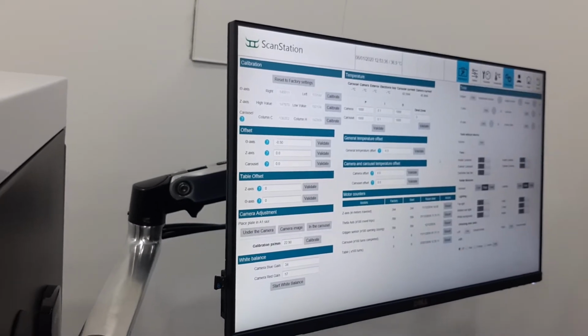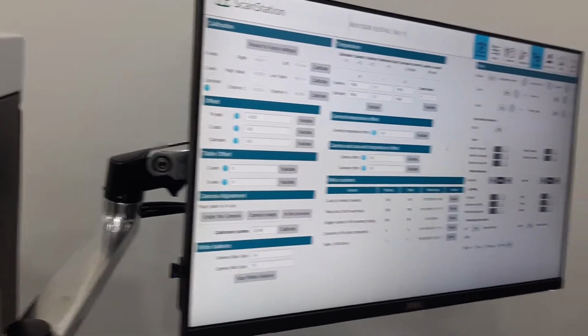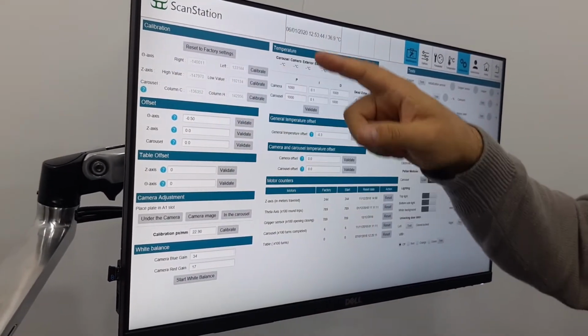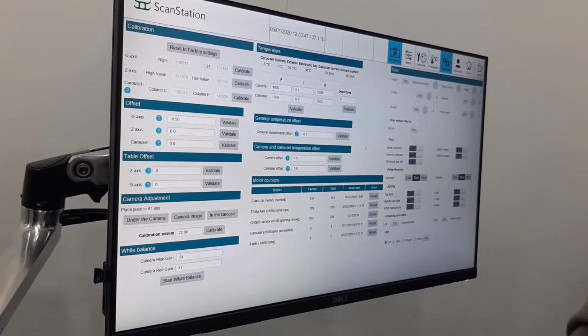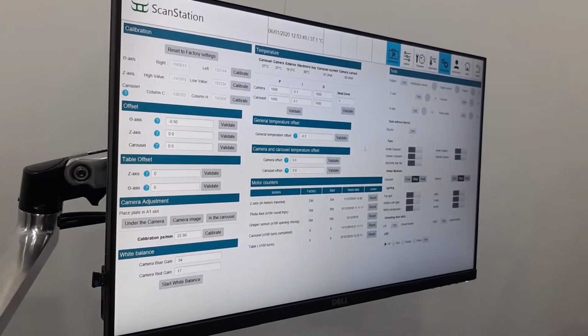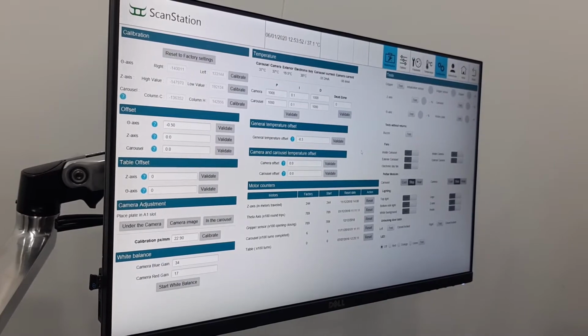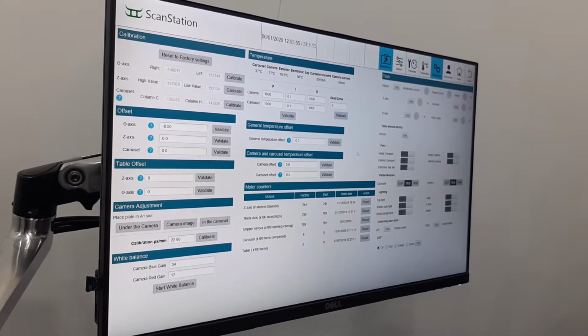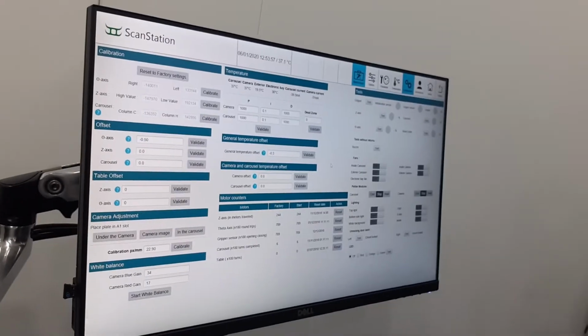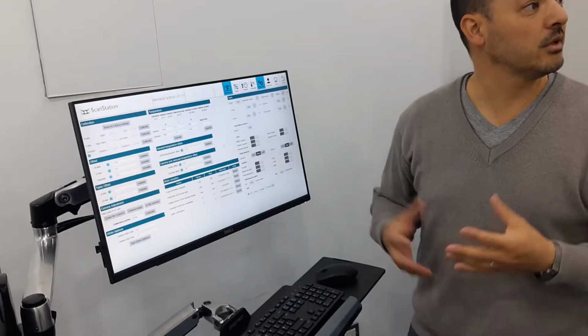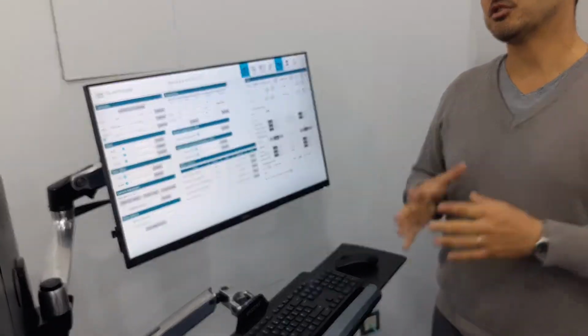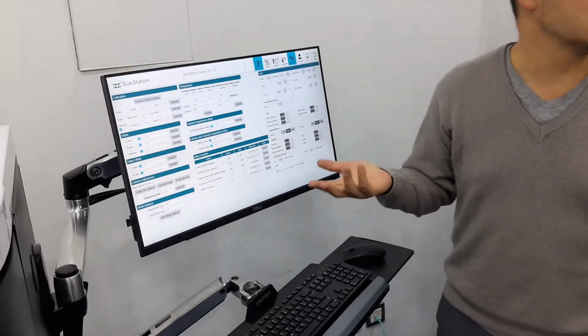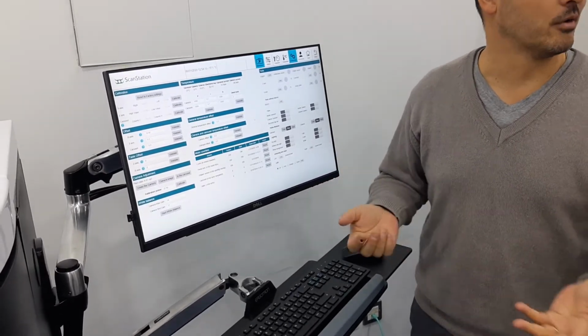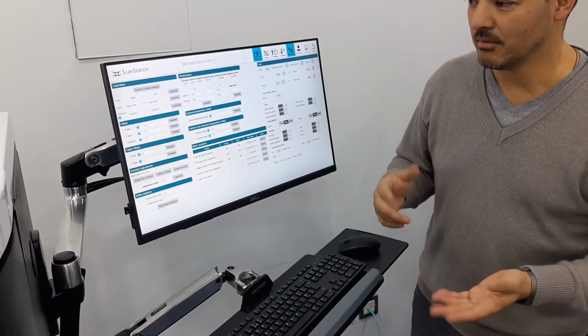So here you go in maintenance mode, and you have a lot of things you can do to test the machine. You can start here. You can calibrate all the different axes of the robot. So theta would be the rotation of the arm, Z is the vertical, and the carousel is the rotating carousel. So the three of them have sensors and they need a calibration. So we do that at the factory. You shouldn't change it, except if you change a robotic part or you think it is necessary. Well, of course. Yeah.